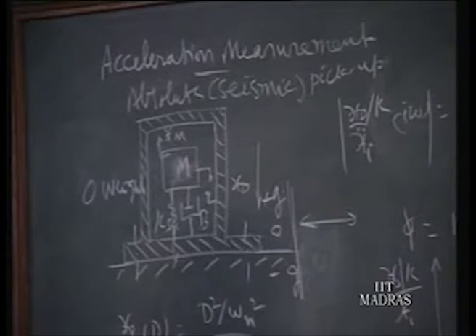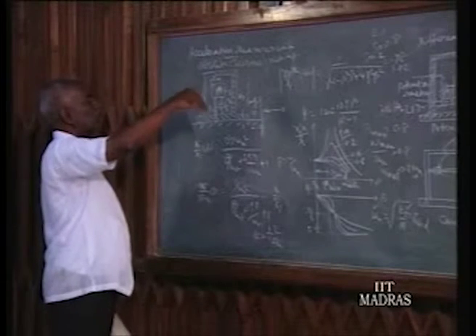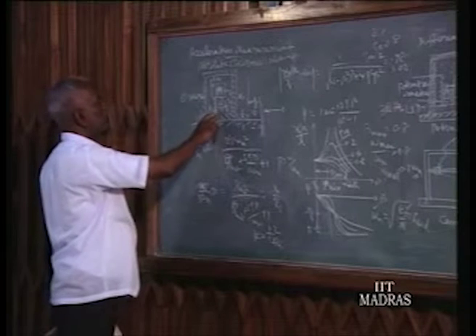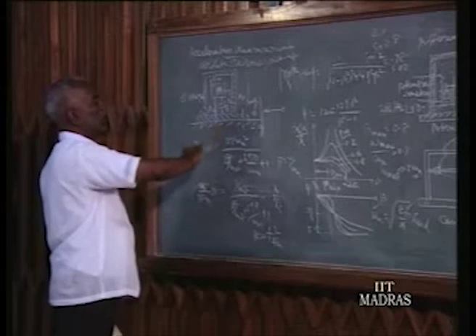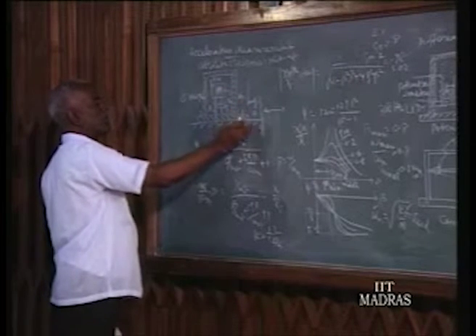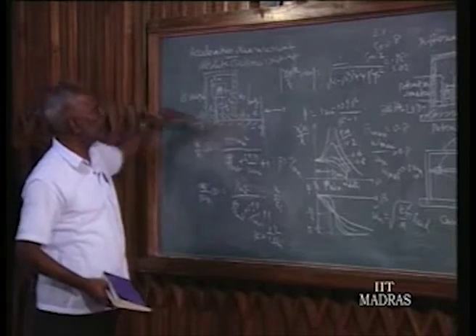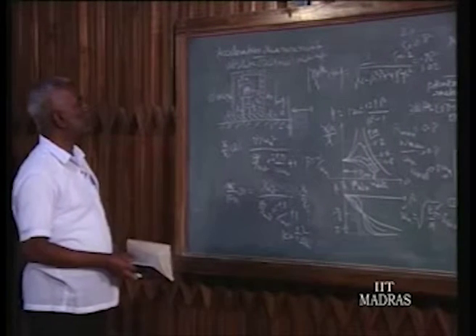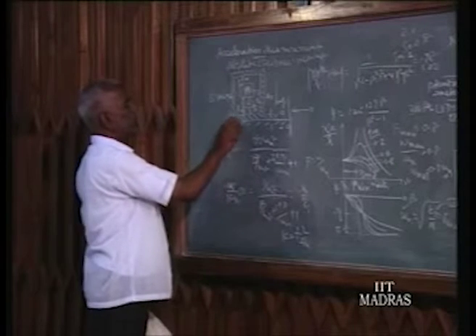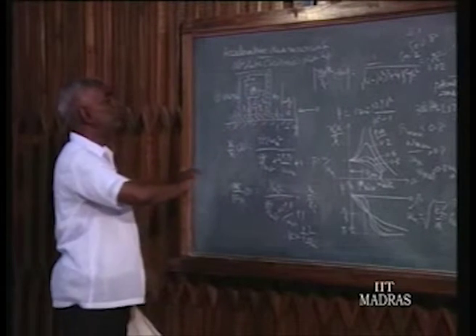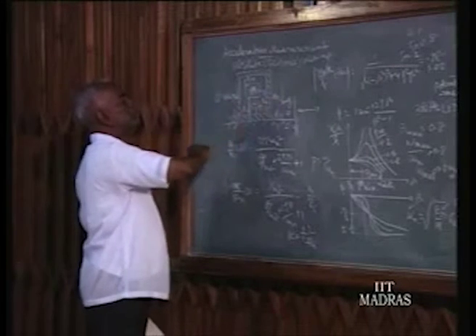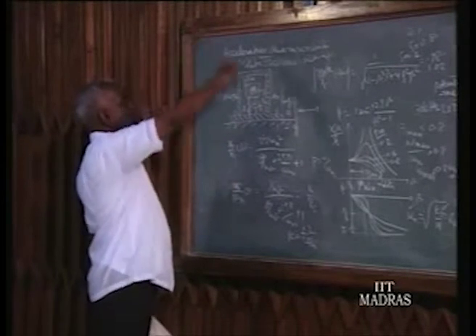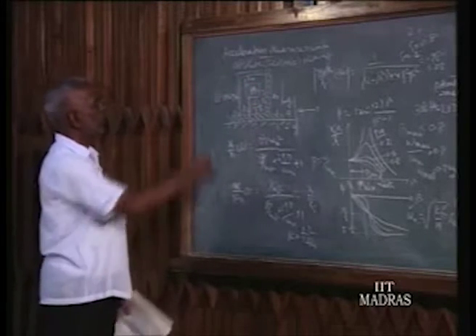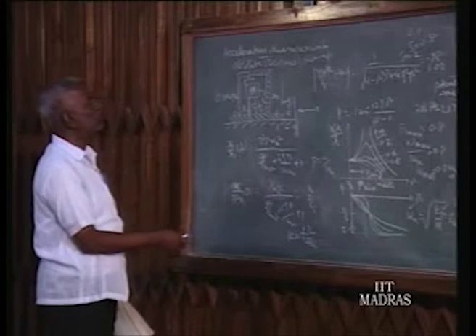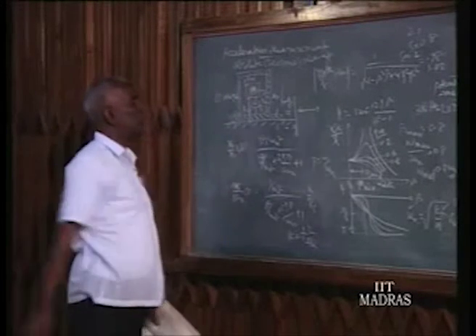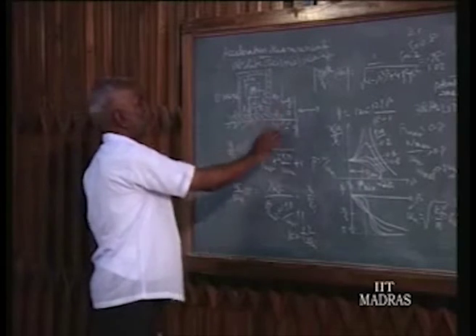If the motion is against G, then you will find you have to subtract 1 G. So for vertical motion you have to be careful. Otherwise, whatever we calibrated by using G is valid for horizontal motion. When it is stationary, it will show G. That is no motion, it is G. For vertical motion, when we go up, the 1 G is already there, that we have to subtract. That's why for a body falling down we have to add 1 G, and for moving up we have to subtract 1 G from the reading. Otherwise, the calibration is valid for horizontal motion.